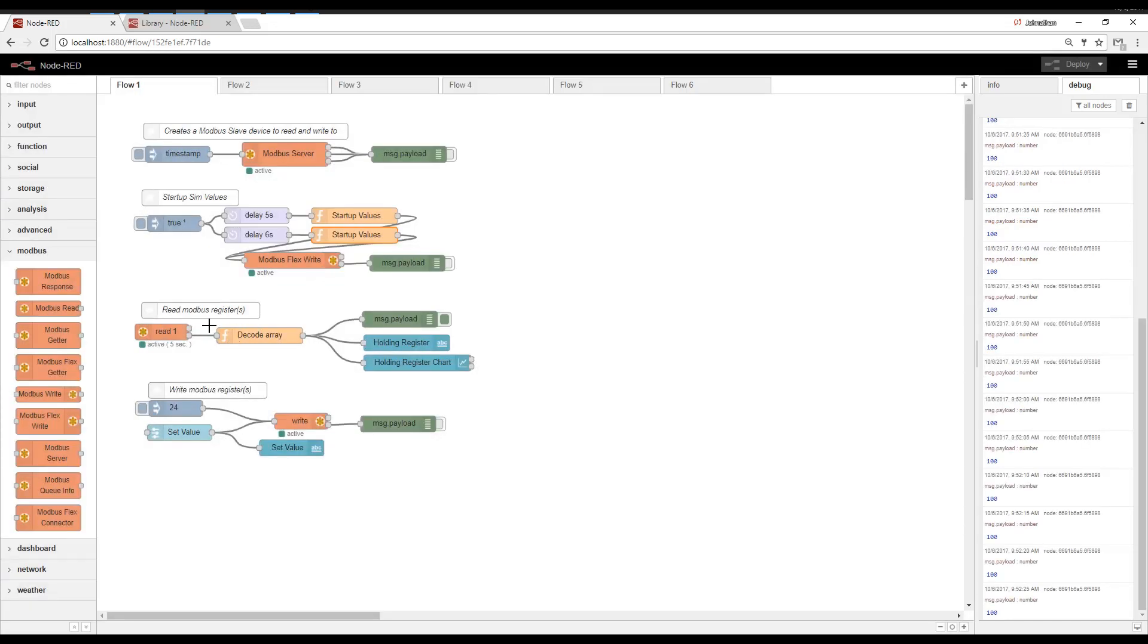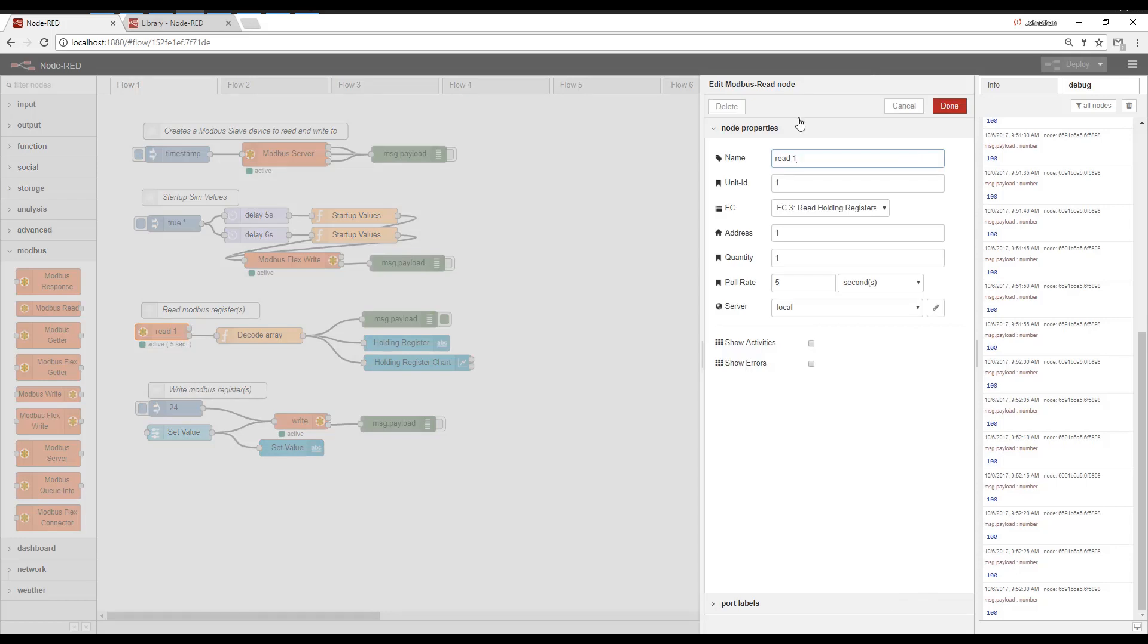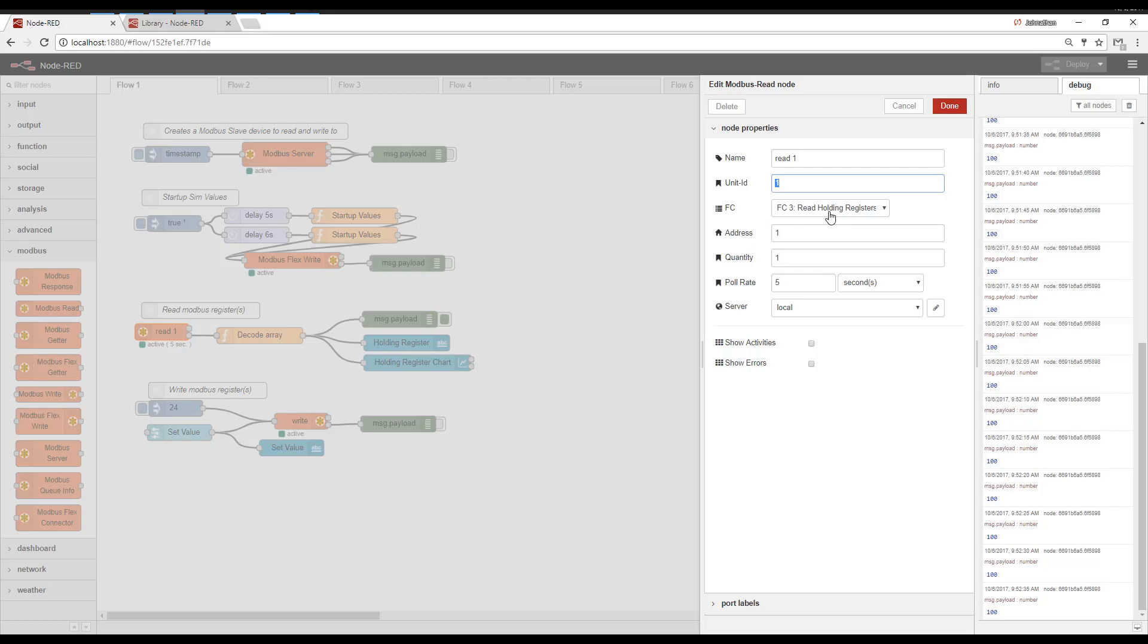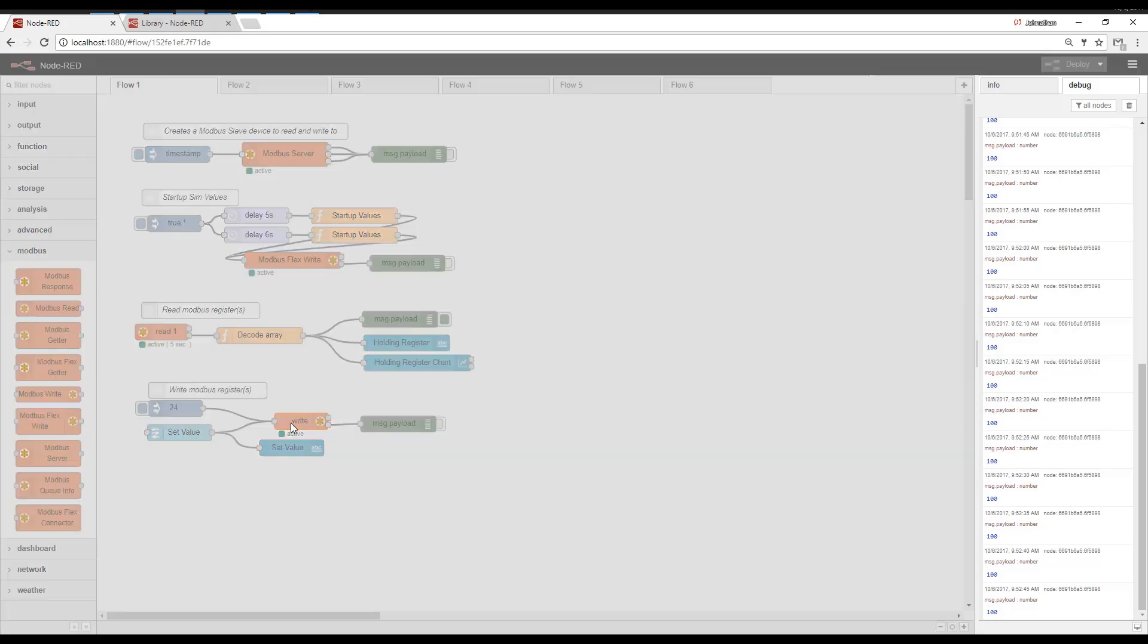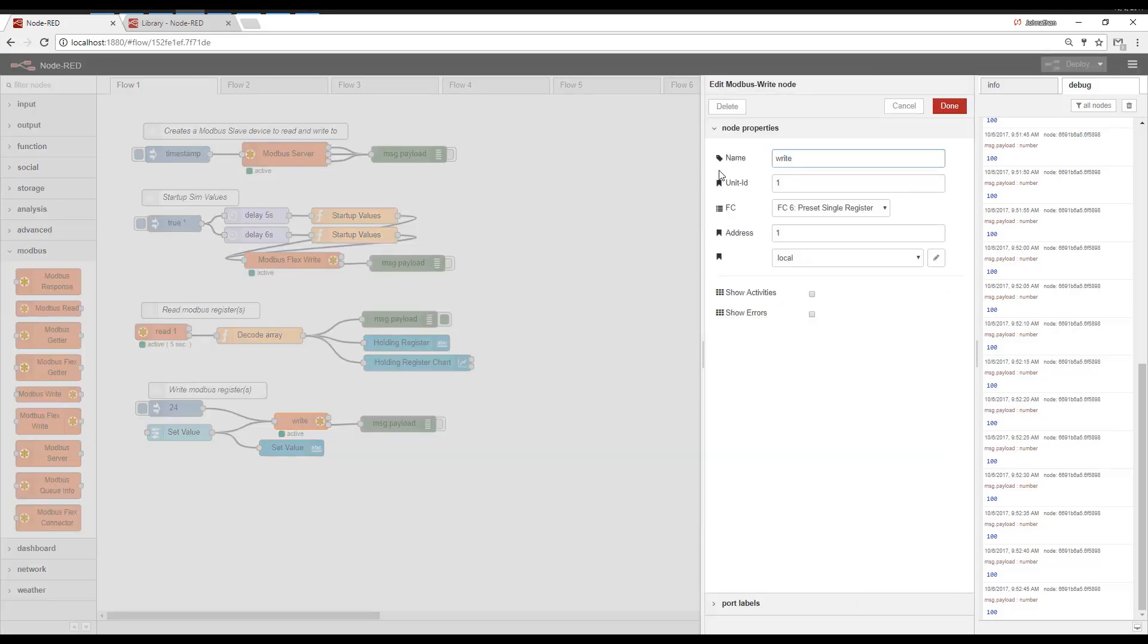Now for a much more simple read and write, here's the simple read. We've got Modbus slave address one. Function code three, which is read holding registers. We're starting with address one and we only need one. And we want to read it every five seconds.